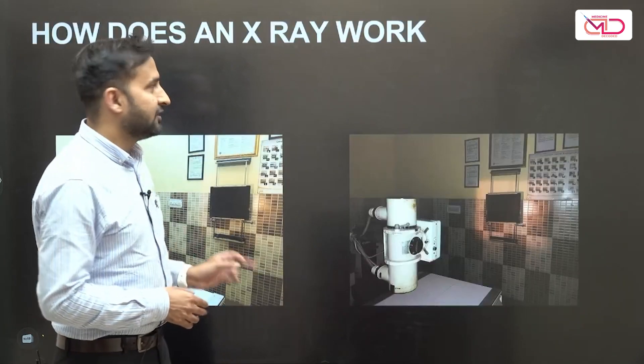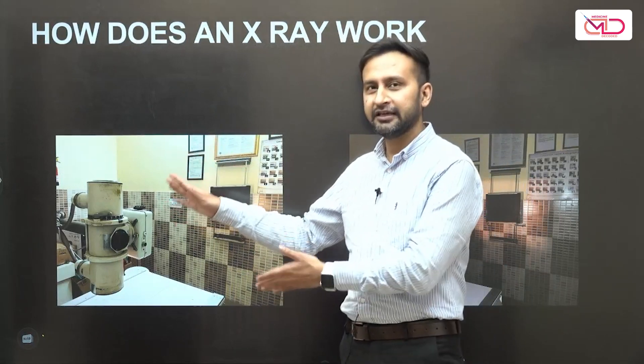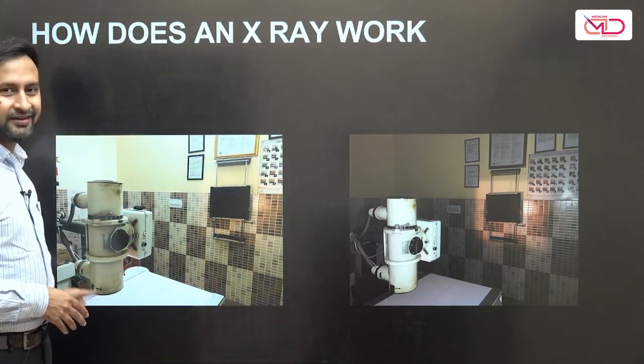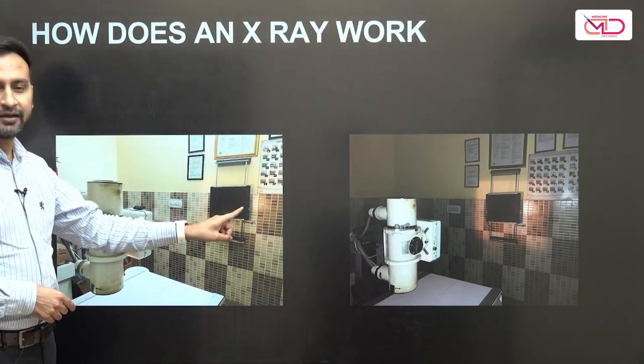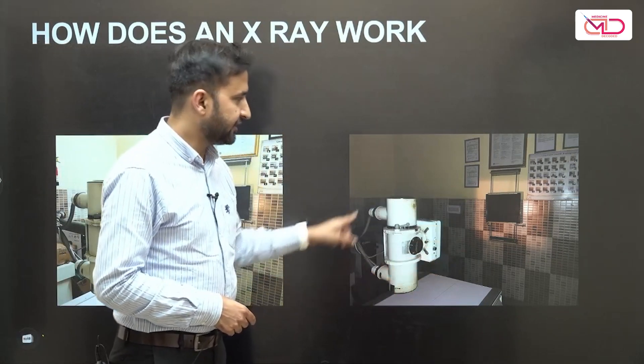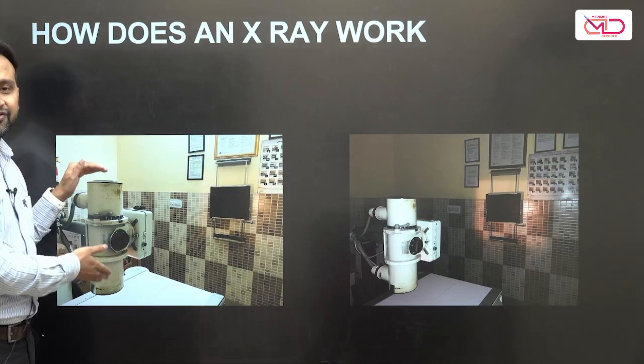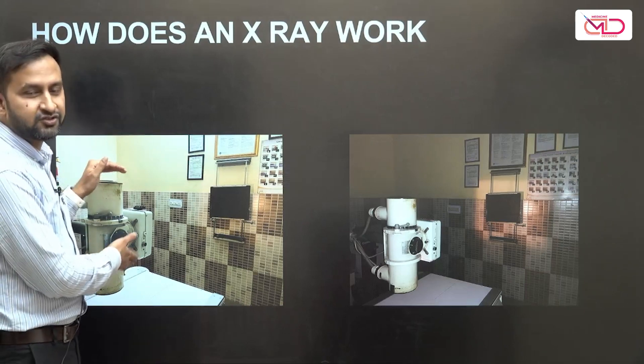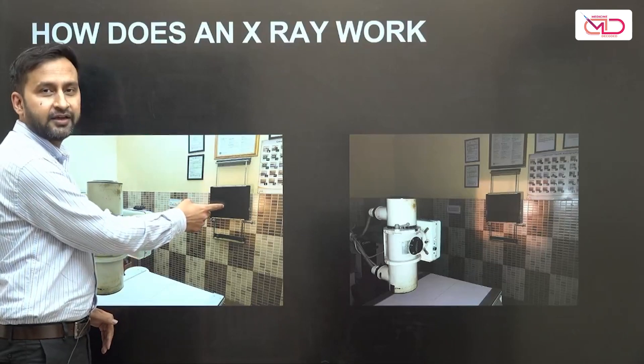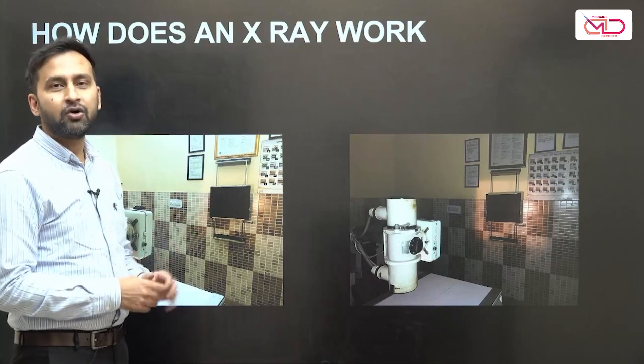The first thing is how does an X-ray work. This is a photograph taken from a conventional X-ray unit room. You can see a white colored structure and a black colored plate at the far end. With the lights off, the white thing is the X-ray tube, which is responsible for generation of X-rays. X-rays pass through this tube, strike the X-ray plate, and finally an image is formed on the plate.